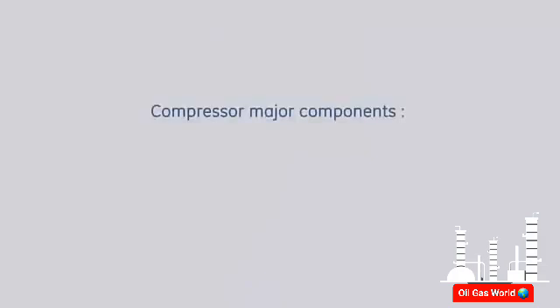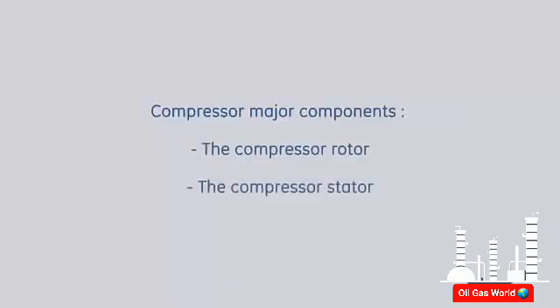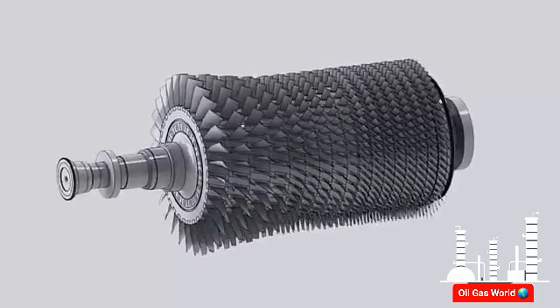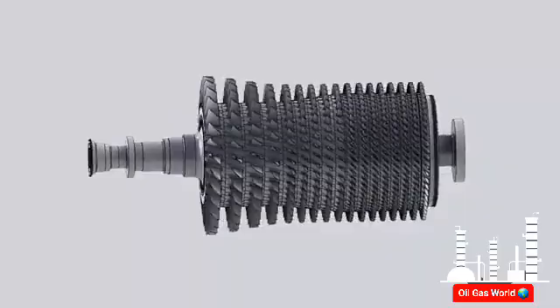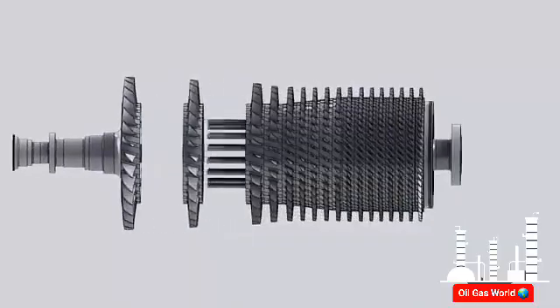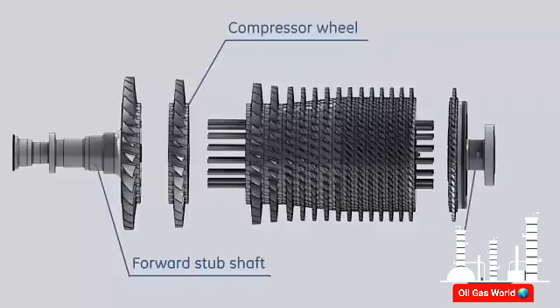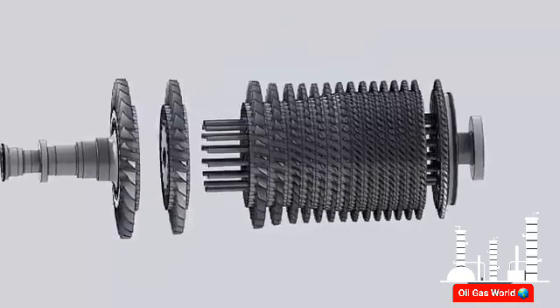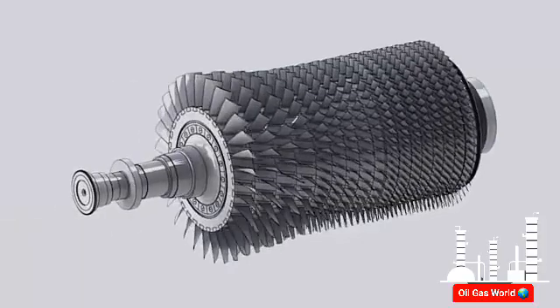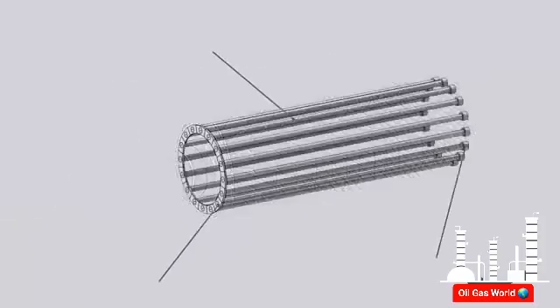The compressor consists of two major components: the compressor rotor and the compressor stator. The compressor rotor has 17 stages of rotating blades. It is assembled of 15 individual wheels and two stub shafts. All wheels are held together with 16 tie bolts and nuts.